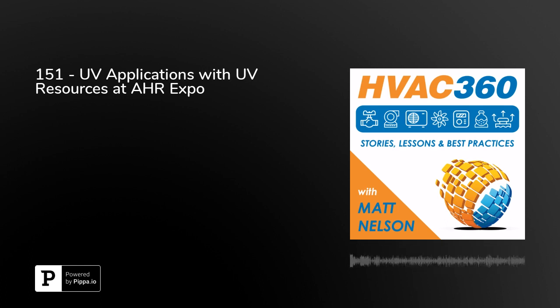So when they're looking at a system and trying to understand how much UV is enough UV, ASHRAE has done a lot of work in their HVAC application handbooks talking about UV. There are chapters on UV in 2 handbooks, rather. And basically what we're talking about is how much UV is enough. It boils down to about 7 watts of UV per square foot of coil.